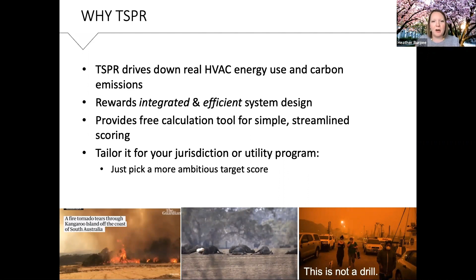So a little bit more about this equation and how TSPR is calculated. Essentially, it's the sum of the HVAC coil loads. If you're familiar with Energy Plus, that would be the ideal loads, or in DOE2, the sum of the zone loads. Those are then divided by the sum of the annual carbon emissions related to heating, cooling, fan, pumps, energy recovery, and heat rejection.